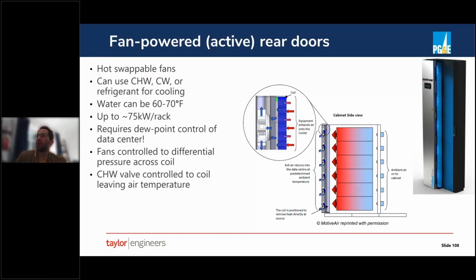Okay, so if we're getting above 20 kW per rack, a strategy that's using either IRC or passive rear doors is kind of getting to the edge of its utility. As an example, we've done some custom IRCs that have roughly 44 kW capacity, which is pretty high for an IRC. So you might be in a situation where you have 2 racks and then an IRC, and then 2 racks and an IRC. A lot of space within your data hall gets eaten up with IRCs. And when we're getting to that density, switching to an active rear door makes more sense.